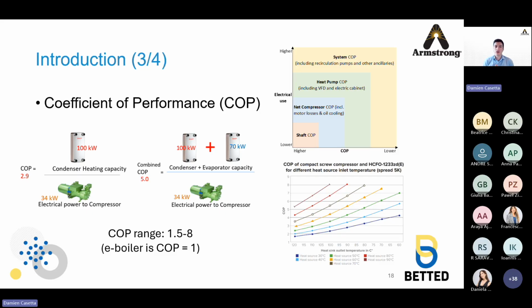To define the efficiency of heat pumps, we have the so-called coefficient of performance, abbreviated COP. That's basically a ratio between what you get and what you pay. What you get is heating capacity, and what you pay is electrical power to the compressor. If you're interested in both the heating and the cooling side, then you add both and you get a so-called combined COP. But then there are a lot of details.